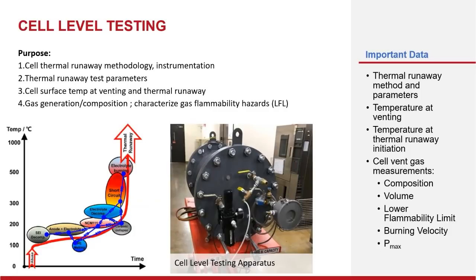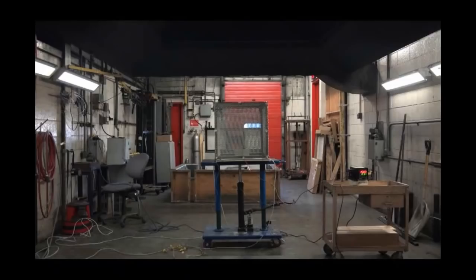We're evaluating thermal runaway, the method and the parameters of it. What is the temperature at venting, and then what are the temperatures when we actually transition into thermal runaway? We're measuring the composition of the gases, the volume of the gases, the lower flammability and the burning velocity. I'm going to show you a video here of one of the initial cell level tests in a lab at UL.